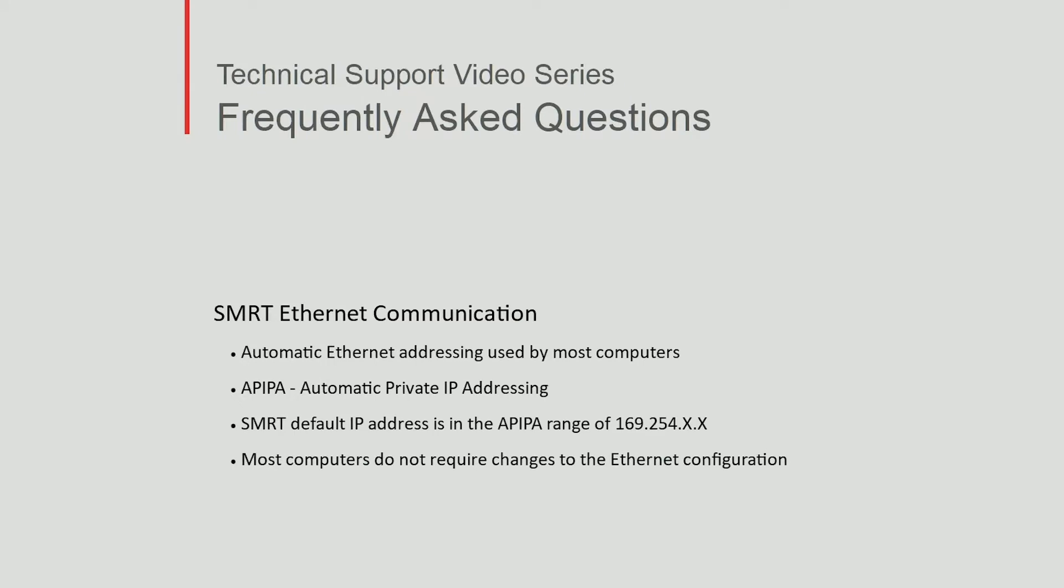Most computers today are configured for automatic Ethernet addressing. If a computer is configured for automatic addressing and it is plugged into a live network which does not have an address server, then the computer assumes an address in the automatic private IP addressing range. The default address in the SMRT is in the automatic private addressing range, which is 169.254.something.something. Most computers do not require configuration changes to the Ethernet port.